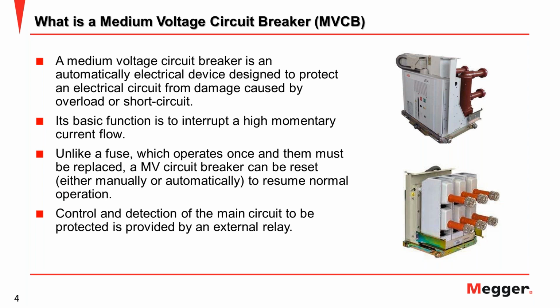Unlike a fuse, a breaker can be operated many times. As we know, a fuse works only one time; after it breaks, you need to replace the fuse. But the breaker you can operate many times because it has a separate control circuit to operate the breaker.